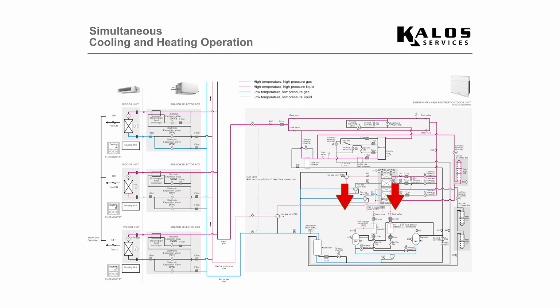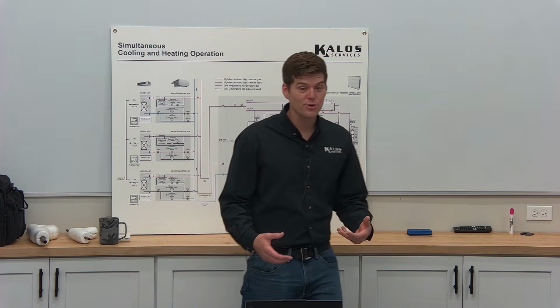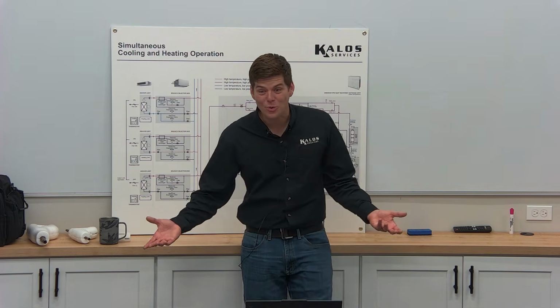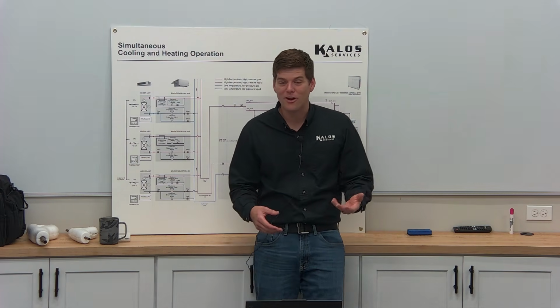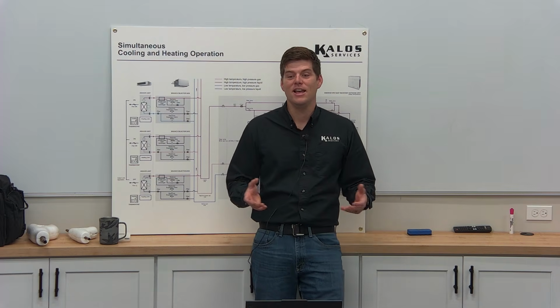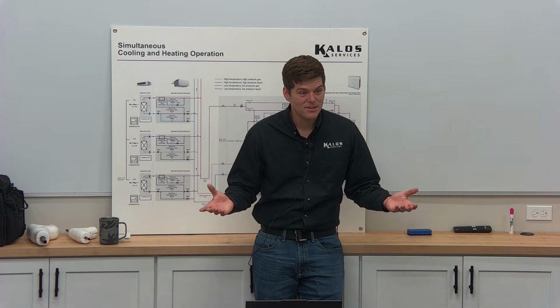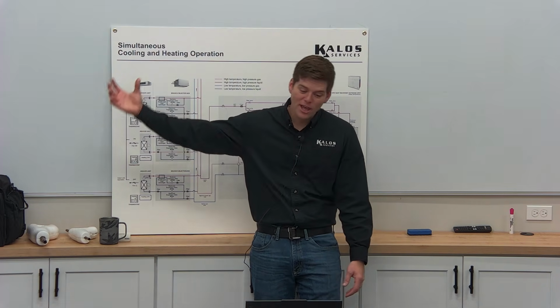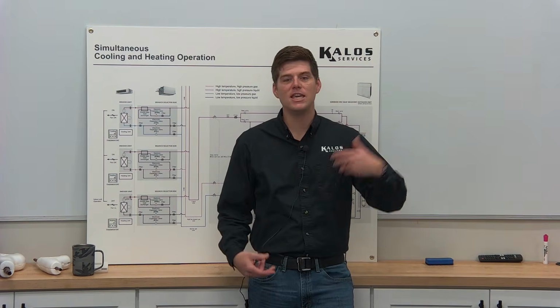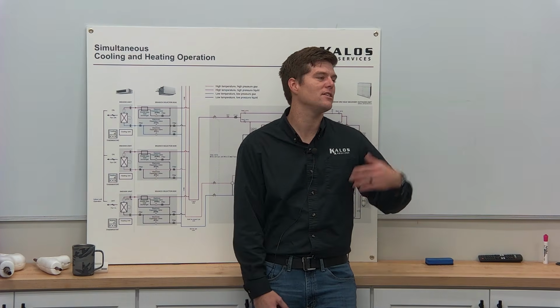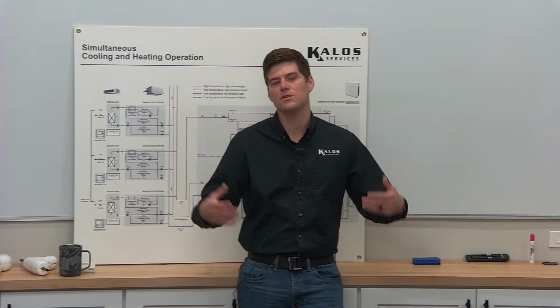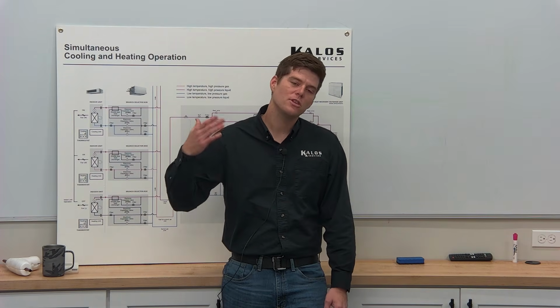It's a compressor or two compressors in an outdoor unit. And guess what? Big shock. The outdoor unit has fan motors. It's air-cooled, right? They make water-cooled VRF, but we're not going to talk about that in this class. It's the same concept. It's using fan motors to pull air across the coil to reject heat, whether that's in cooling, whether that's in heating. Obviously, those premises don't really change that much, but those are the basics.